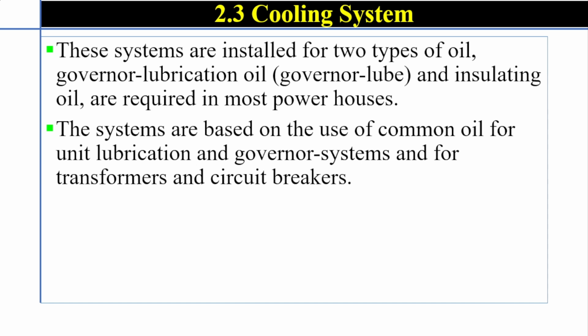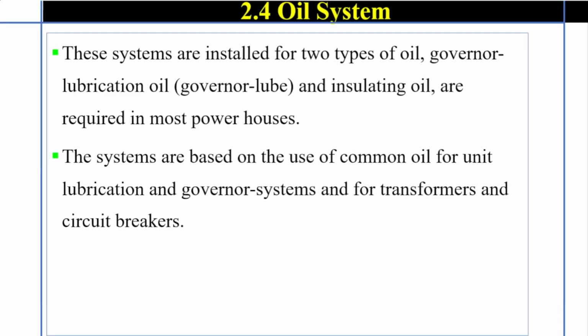Oil system. These systems are installed for two types of oil, governor lubrication oil or governor lube, and insulating oil, which are required in most powerhouses. The systems are based on the use of common oil for unit lubrication and governor systems and for transformers and circuit breakers.